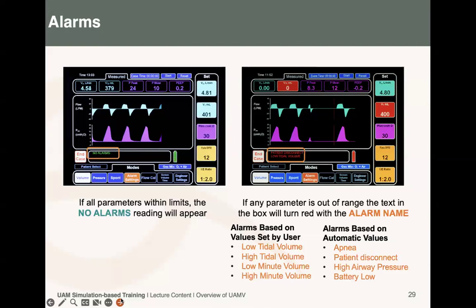So the machine has got other features which you can set. Now discussing more of the alarms. Based on the user setting, you can set your low and high tidal volume, low and high minute volume, so that when the machine is below or higher than the set value, it can tell you. But also the machine has got automatic alarms: apnea, patient disconnect, high airway pressure and battery low. These are all made to make sure the patient is safe.